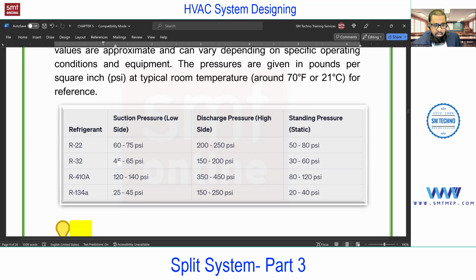You see, for R32 compared with R22, this pressure is different. And you see, for R134A, the pressure is less compared with R22 or R410A, in the suction and discharge line. So this pressure rating also depends on the type of refrigerant. These four refrigerants are commonly used in actual practice for split, window, and even chiller. In chiller, you'll find R134A; in chiller, VRF, and package, you'll find R134A, R410A, or even R32. R22 you can find in window and split only, not in the big units.